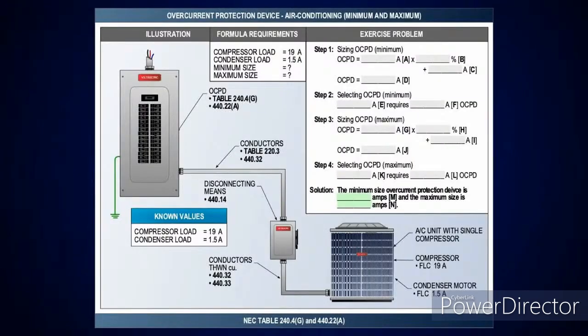One thing I want to mention too is when you're sizing on these AC units, all you have to cover is the minimum circuit ampacity. So if it says, like, a minimum circuit ampacity of 21 amps, you think, oh man, I can't put a number 12 on there. That's not true because the AC unit has 75 degrees C terminals. So all you have to do is go to that 75 degrees C column, and then you just go to that value, which number 12 is good on THHN for 25 amps, and then you can use a number 12 over 20 amps as long as you're in that 240.4(G) column with the AC unit.